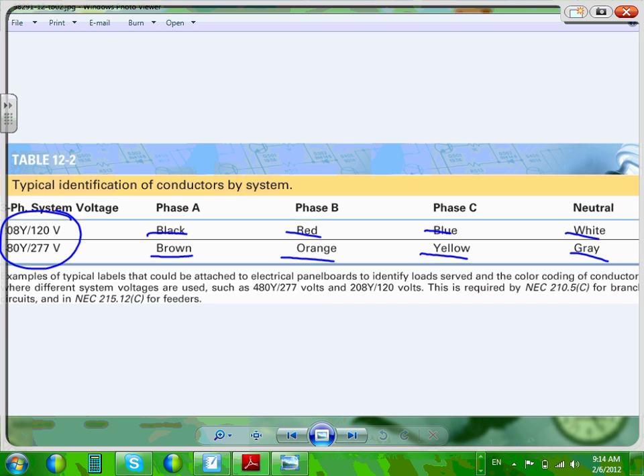If you have two systems in your building, we don't have this. If we have two systems in our building, then that color code must be placed on every panel in your building. See that schedule here? I have to label it right at the face of every panel that I have. Why? Because an electrician walks in, they need to understand the color code in that building. If you have two voltages, or two systems, like 208, 120, 480, 277, you have to have a label. If you only have 208, 120, you don't need to label your panels with the color code of the system. Attach this label directly to the face of every single panel in your building.